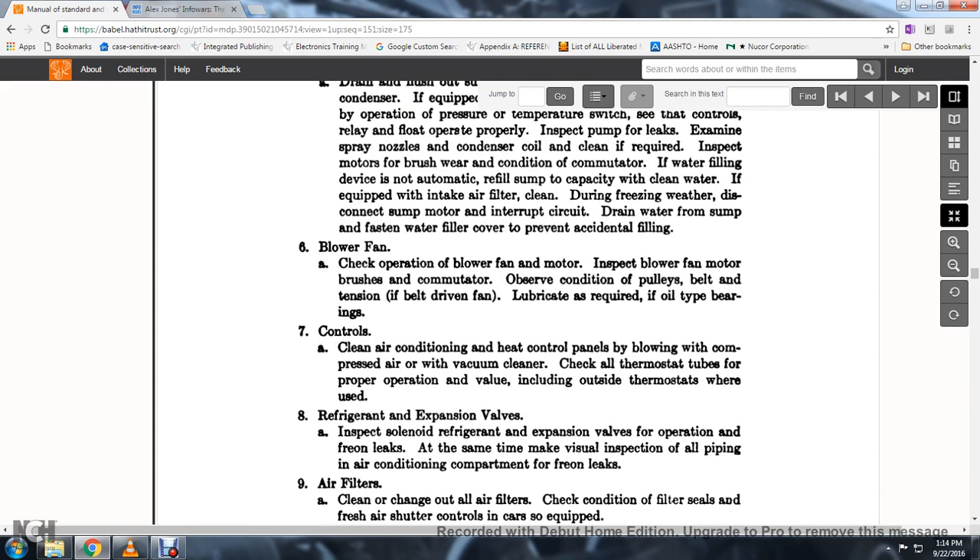6. Blower fan: check the operation of the blower fan motor; inspect the blower fan, motor, and brushes. Observe the condition of the pulley, belt, and tension of the belt-driven fan. Lubricate as required if oil type bearings.